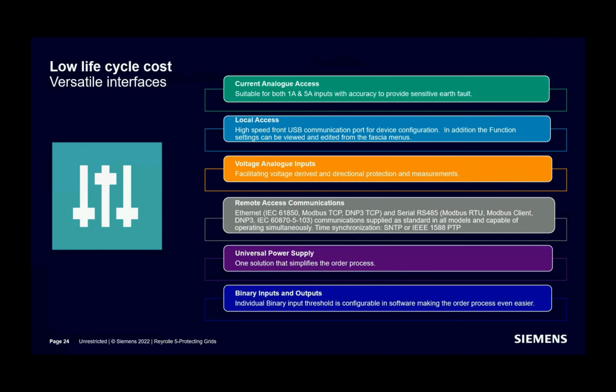The 7SR5 relays serve IEC 61850 together with Modbus TCP and DNP3 TCP at the same time. So let's assume a substation with a local SCADA which uses Modbus TCP. So 7SR5 will serve this local SCADA via Modbus TCP, and let's assume a central control center far away from this substation, and it communicates through IEC 61850. So the same 7SR5 device will communicate through Modbus TCP to the local SCADA and communicate through IEC 61850 to the control center. It's all possible. Or you can choose DNP3 TCP at the same time instead of Modbus TCP. And the redundancy types for IEC 61850 are RSTP, meaning ring type, or PRP or HSR. These are all supported for full communication reliability.